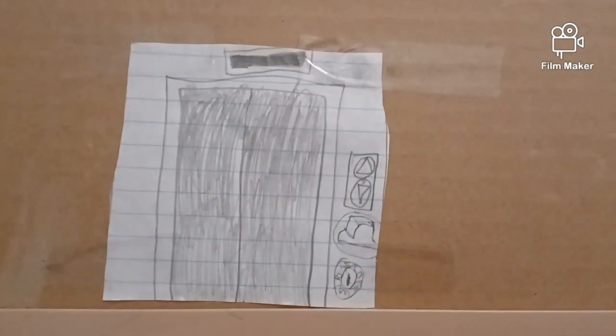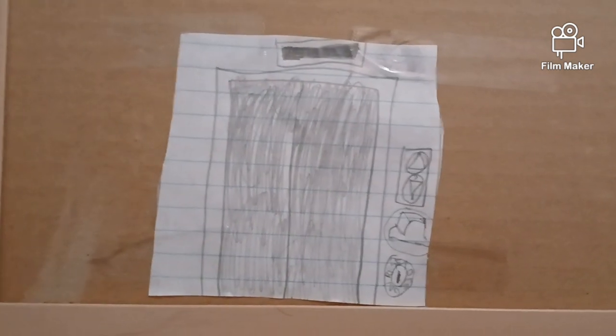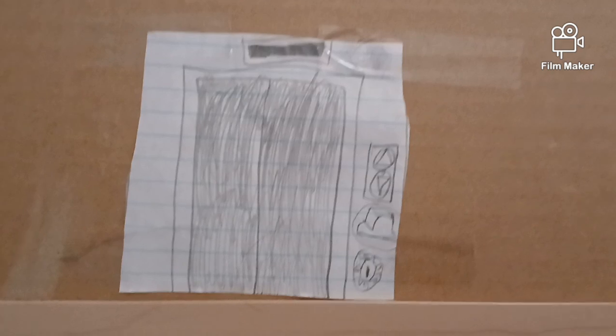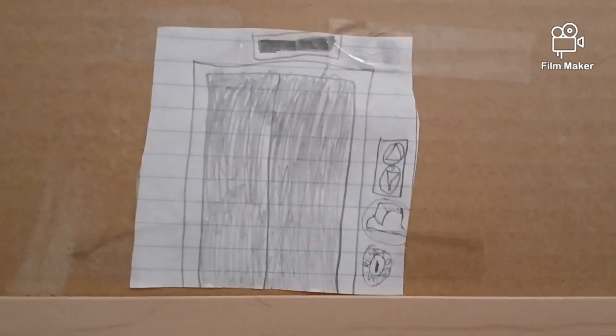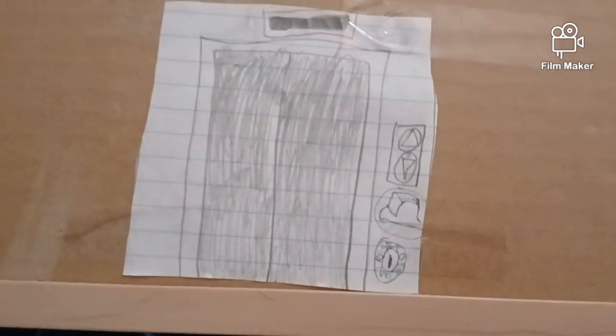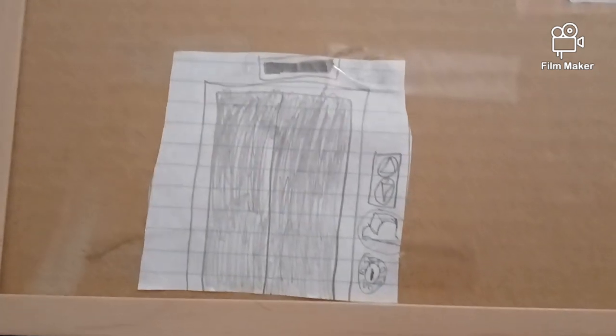And then you got your elevators that are wired into a fire alarm system, so that when an alarm goes off, the elevator will enter fire recall mode and relocate to the main re-entry floor, and just stay there with the doors stuck open until firefighters arrive to use it to get to where they need to be, such as the floor that the fire alarm was activated on.